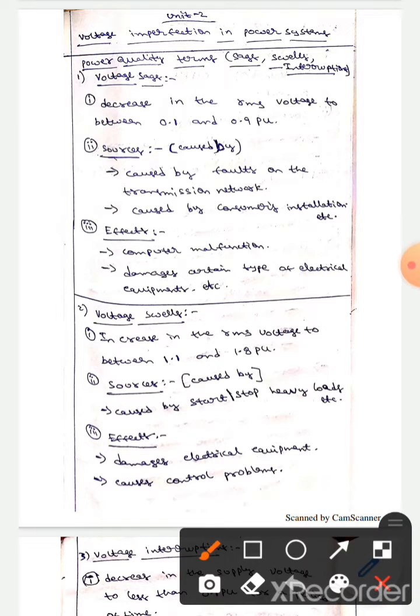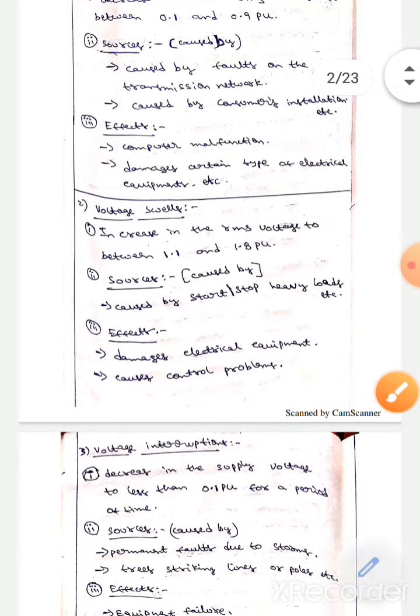The first one is voltage sag. It is a decrease in the RMS voltage to between 0.1 and 0.9 pu. It is caused by faults on the transmission network and also by customer's installation. The effects are computer malfunction and damage of certain types of electrical equipment.